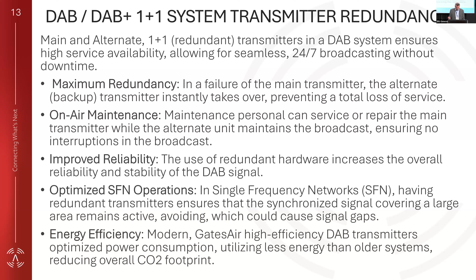How does it look? You basically have two individual transmitters connected to a switch and a controller. The controller monitors both transmitters and switches between them as needed, manually or automatically. You can define how the switchback works - you want to avoid a hysteresis or toggling between the two transmitters if there's a problem outside, causing the system to switch back and forth all the time.